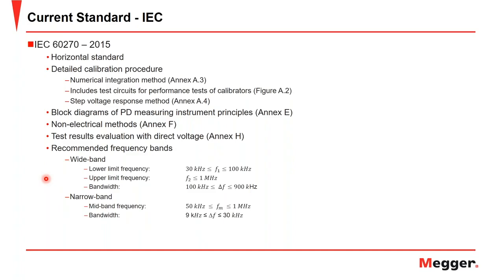Again, these bands correspond to the partial discharge method of measurement as well as the medium of measurement. So again, going back to when we were talking about gases and the rise time of nitrogen versus SF6 affecting the frequency bandwidth that you'd measure, that's where these recommended bandwidths come into play.